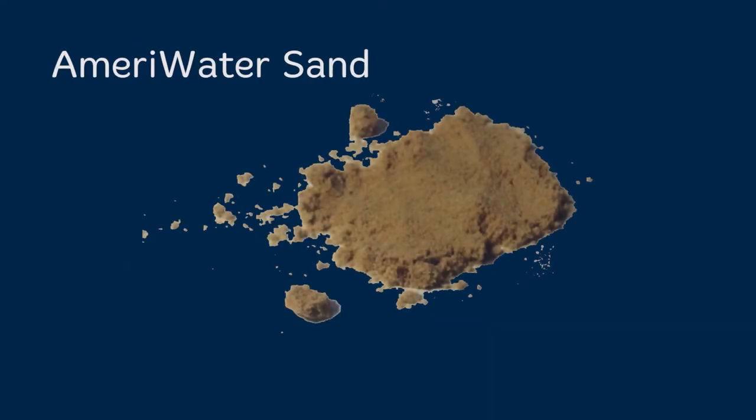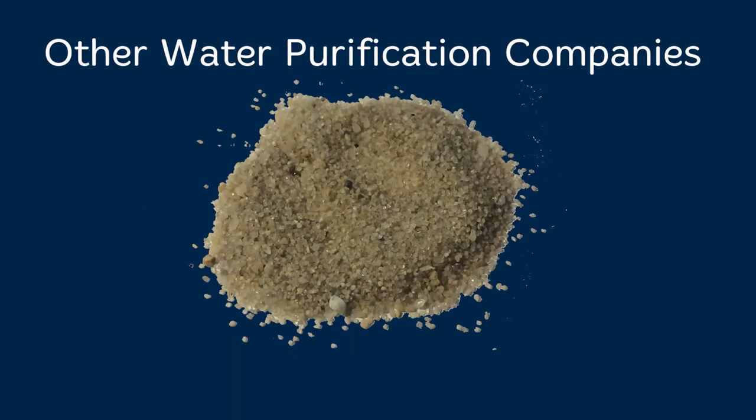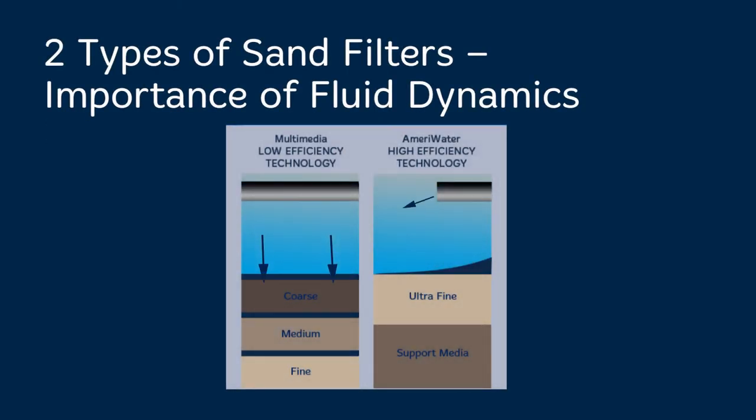This is the sand needed to remove half micron particulates. This is not. Ultrafine sand is what is required for half micron filtration. Filters must have a specific fluid dynamic, construction, and design in order to effectively utilize ultrafine sand, resulting in half micron particle removal.